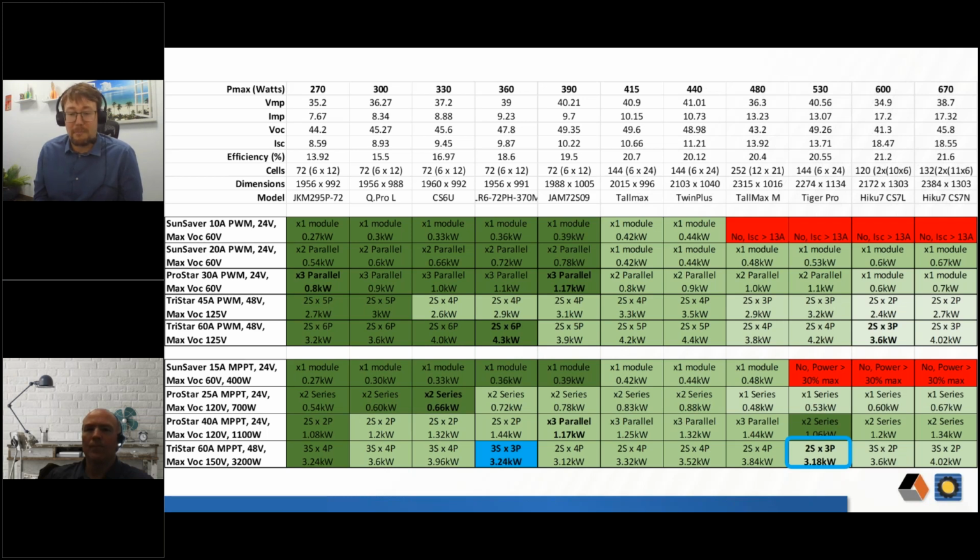So you sort of get all the penalties in terms of design cost with the full 30% output, but you as a consumer or a user are only seeing the 5% benefit on average that bifacial is actually going to produce in a real world application for us. Maybe 5 to 10%, but I certainly don't know anybody that's banking on anything more than that when they're doing the design reliability analysis. So it's a whole other variable in all this. You've got to treat the worst case scenario electrically, but from a design performance standpoint, you kind of got to take the conservative approach and stick with the minimum benefit, which is in that 5 to 10% range. Great question, though.